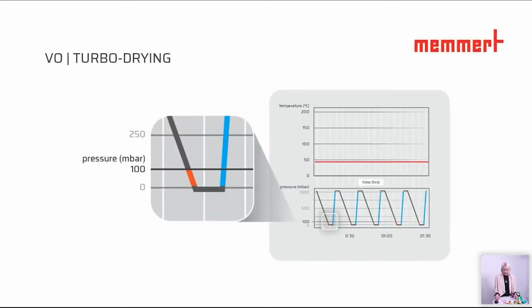Okay, let's go further. When we look at this turbo drying process, what does it actually mean? This means when we go down in pressure, as we can see here on the left image chart, then we get evaporation, and you can see here at 100 millibar the evaporation starts. Why does it start here? Because on the right side, we see a temperature setting which is below 50 degrees. And actually, I can tell you, if you work at around 100 millibar, then water evaporates at around 46 degrees. So here, already at 100 millibar, the evaporation process starts.